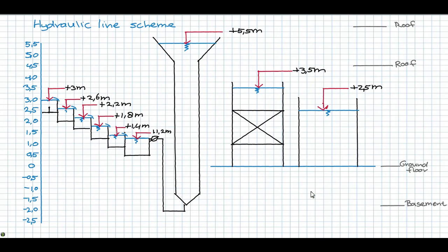Knowing the heights of the different treatment processes and the hydraulic resistances, we can draw the hydraulic line scheme. From the hydraulic line scheme, we can determine the total building height and the number of pumping steps.